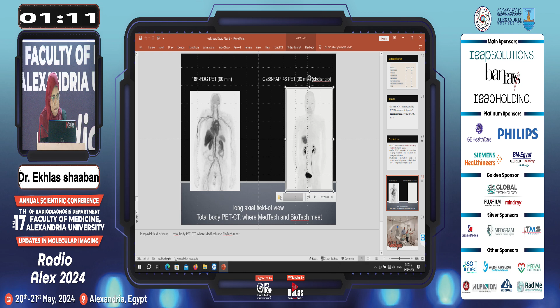It's a scanner that's able to scan the patient with one bed position, so we can decrease the dose of administered tracer. We can decrease the scanning time. We can have dynamic study. And I think it's promising because the most drawback of PET-CT is the higher dose of radiation and the use of radioactive material. So with this machine, with long axial field of view, we can reduce this weak point of PET-CT. And thank you.